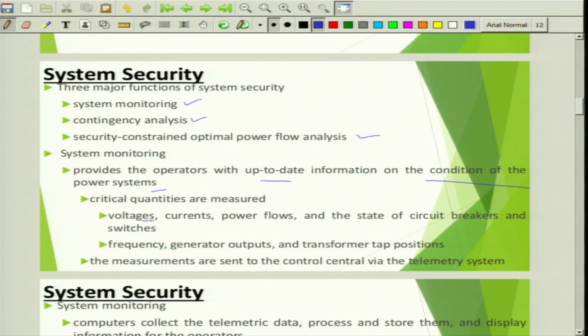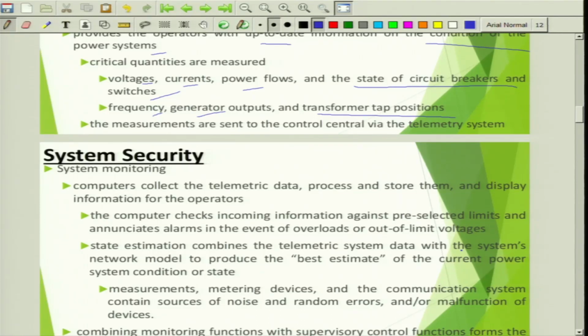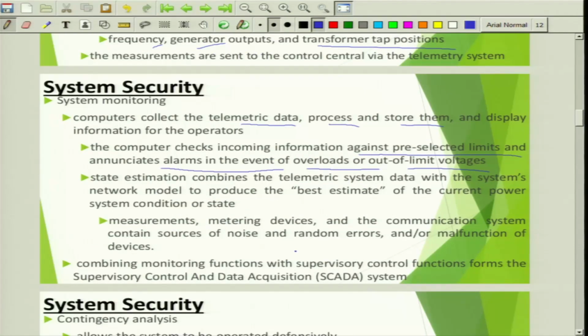What are those critical quantities? Like voltages, currents, power flows, and the state of circuit breakers and switches, and also frequency, generator outputs, and transformer tap positions. These are some of the critical parameters. The measurements are sent to the control center via the telemetry system, and action is taken. Further, the computers collect the telemetric data, process and store them in the central system and display information for the operators. The computers check incoming information against pre-selected limits and sound alarms in the event of overloads or out of limits violations. State estimation combines the telemetric system data with the system's network model to produce the best estimate of the current power system condition or state.